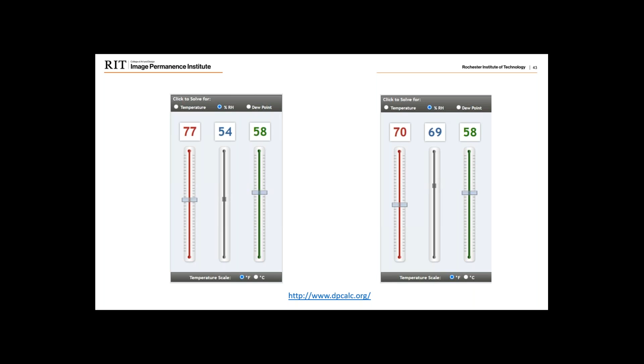So if we run those units at the same dew point and lower the temperature even to 70 degrees to make it more comfortable, our relative humidity jumps up to 69. If we lower it further, say to 68 or even 66, it gets even higher, putting us into pretty uncomfortable, even dangerous territory for our collections, somewhere we don't want to be. So it's something to keep in mind that bringing in portable air conditioners can cause more issues than we thought.